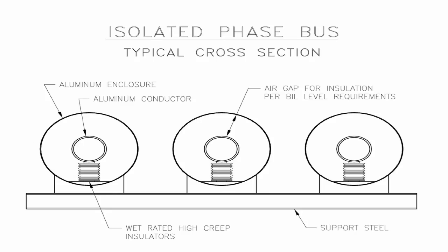This is a typical isolated phase bus system. It consists of an aluminum enclosure with an aluminum conductor. It's mounted in there with a wet rated high creep insulator. They can actually have moisture in the bus and it will not flash over. This assembly is set on support steel, and it actually uses air as a gap in there for the insulation, and that gap is set per the BIL level requirements.